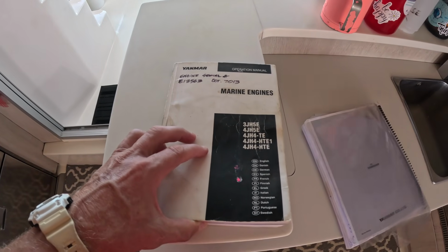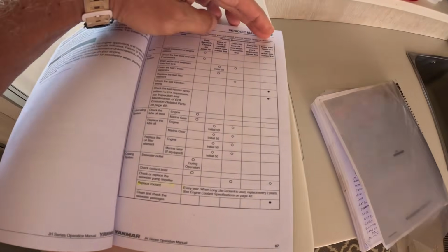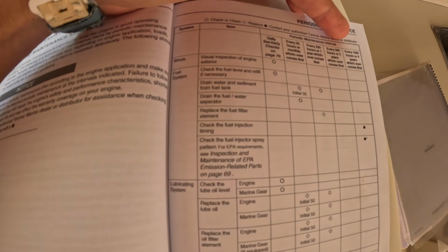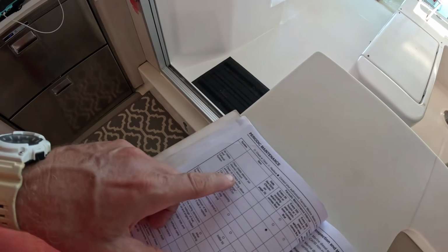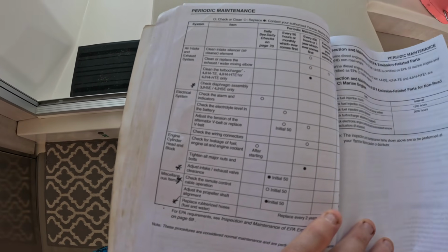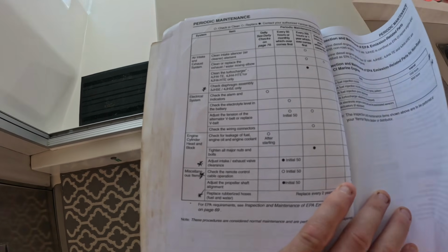Here is the manual for our 3JH5E. Under periodic maintenance, you'll see sections for the fuel system, lubricating system, and here, the cooling system. There's no mention of replacing the heat exchanger gaskets - it just says to replace the coolant, replace the seawater pump impeller, and check the coolant level. It also talks about when to replace the mixing elbow and exhaust, but nowhere does it mention the heat exchanger and replacing those gaskets. So this is a real gap.